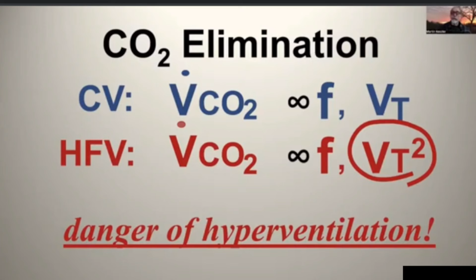In conventional ventilation, it's the PIP that's adjusted. In HFOV, of course, it is the amplitude that is adjusted. So again, the tidal volume is measured. It's averaged over 10 seconds or so. It's compared to the target tidal volume, and the amplitude is then adjusted up or down to maintain the set tidal volume. The amplitude limit, just like the pressure limit with conventional, has to be set, typically about 5 centimeters above the current value, maybe 10 in some instances where there's more variability.